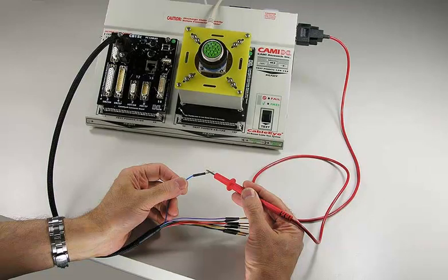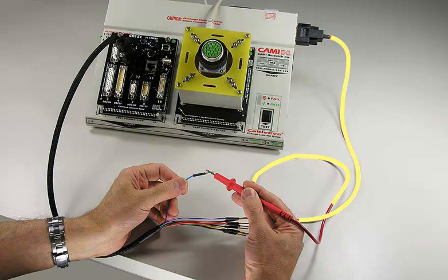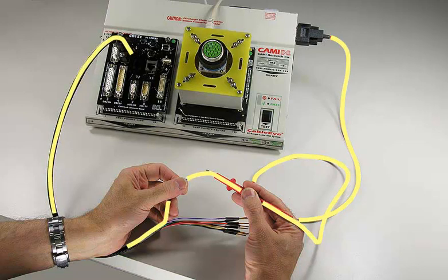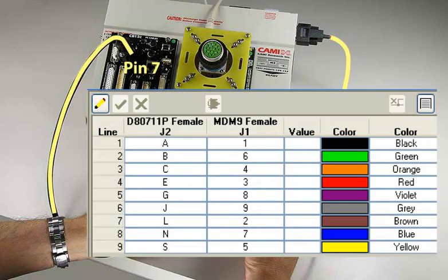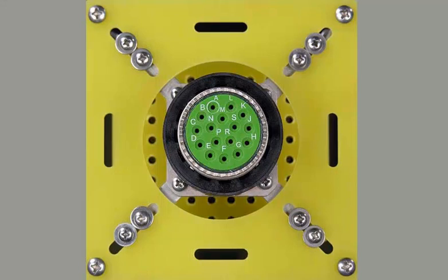When you touch the probe to any pin selected at random, a signal passing from the probe into the wire enters the CableEye tester, where it's picked up, identified automatically based on the DB9's pin number, and then looked up in a wire list to see where it should be connected. The appropriate LED lamp then flashes in the light director to identify the target, and the cavity number is read aloud.